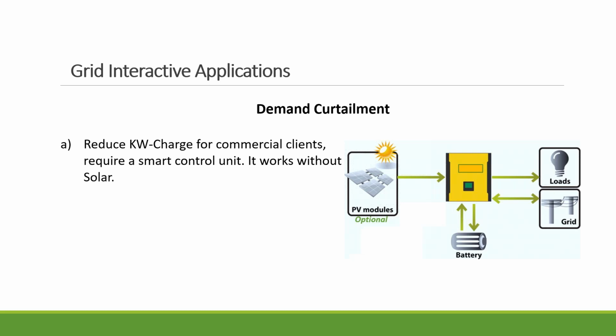Just using PV by itself can lower your consumption, but not the kW charge. If you add a battery energy storage system, it will frequently measure your consumption, and once it senses you're going above your target—say 100 kW maximum—the energy storage system will start functioning and lower your kW to keep you within that target line.